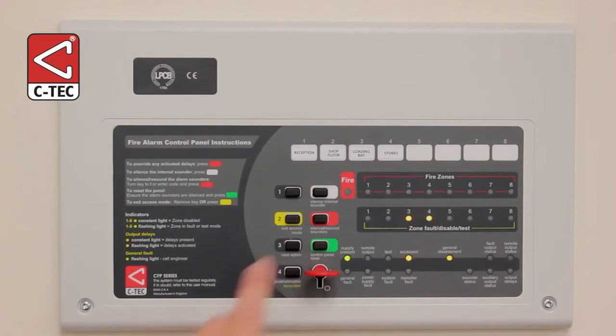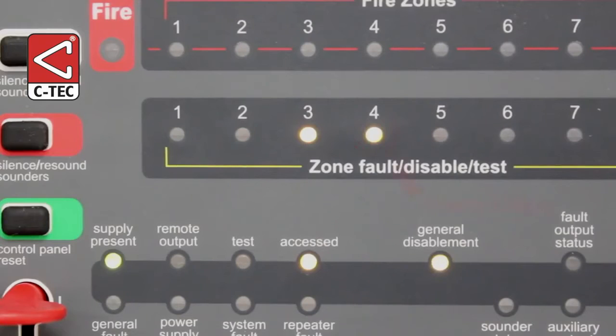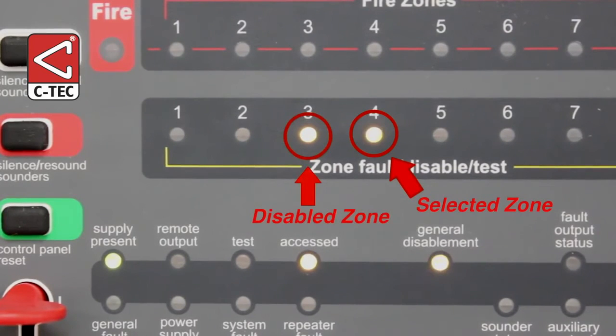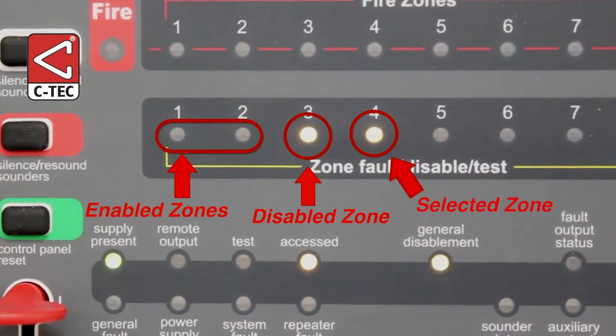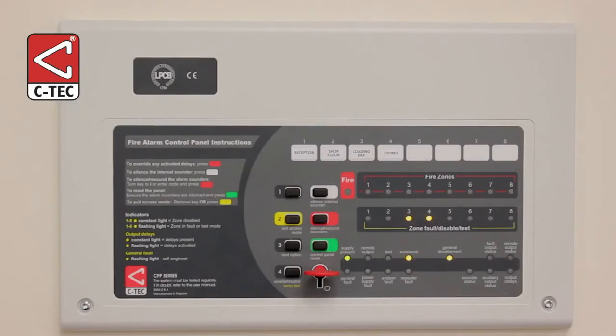This moves the selection process onto the next available option, in our case, Zone 4. The fault light for Zone 4 is flashing. Meanwhile, the fault light for Zone 3 is lit steady to confirm it's disabled, whilst Zones 1 and 2 lights are off to confirm they are enabled. The selection process can also be used to enable and disable the panel's fault output, remote output, all of its alarm devices, its auxiliary output, or any delays programmed into the panel.